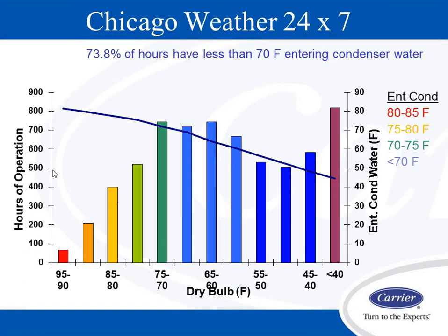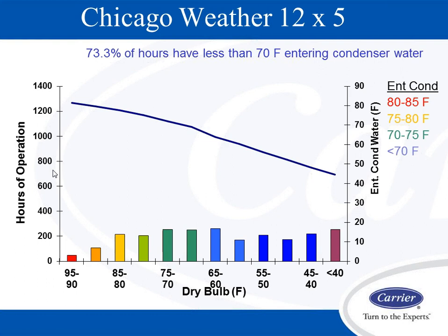As I mentioned before, we have a ton of hours that can operate lower than 70 degree entering condenser water. On a building that operates 24/7, 73.8% of the hours we can operate with less than 70 degree entering condenser water temperature. In a building that's operating 12/5, we have 73% of the hours that have less than 70 degree entering condenser water. When you enter into air side economizer, it's slightly less than that, but it's still a high percentage of building operating hours with cold condenser water.